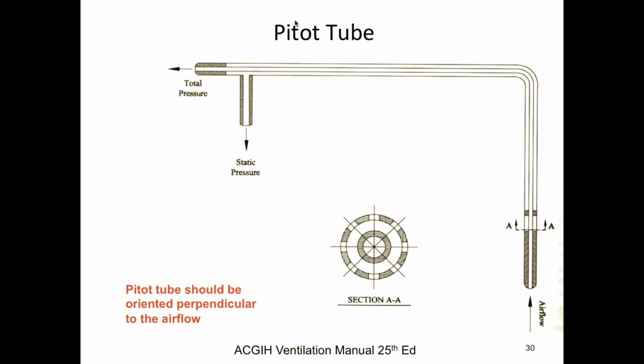This thing measures both static pressure and velocity pressure. And the way is from the movement, right? Velocity pressure is directional. Static pressure is omnidirectional. The way that this works is that if I put this in here and turn it, it's going to be facing this direction. And we can connect the tube here and measure the pressure of air moving through this ductwork when the fan's on and going into this end of this tube. Is that total pressure or velocity pressure or static pressure? Which is that? What is that measuring when the air's hitting here?